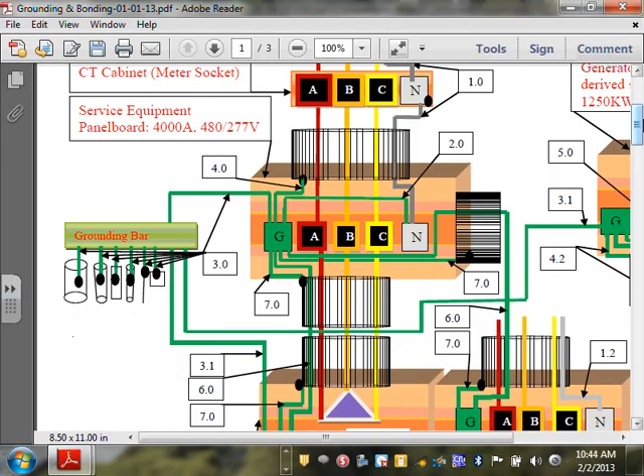You have to bond the metallic conduit to the enclosure. We did that one. You have to bring all your grounding electrode systems into the switchgear, either by grouping them and bringing one home run, or individually bringing them to the switchgear. And we did that one. Any comments, any questions? Does anybody do it differently? So what we covered right now is 2 chapters in the book, just about the main and so forth. Okay, now we'll go to one branch, guys.